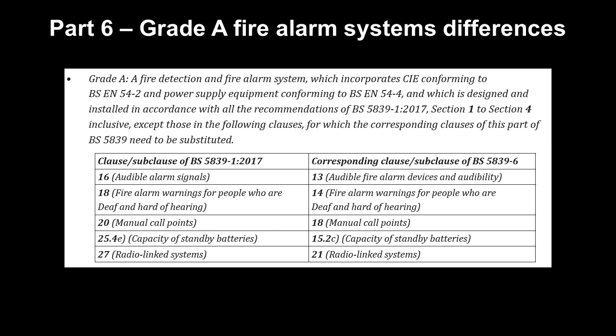What you do is, when you've got a system that requires a grade A fire alarm system, you are installing that system to part 1. This is the important thing. So if a grade A system is specified, you install that system in that premises to part 1, fire alarm panel and everything else. However, there's a little list here that lets you swap clauses. So for example, in part 1, on clause 16, audible alarm signals, you don't use part 1, clause 16, use part 6, clause 13, and so on.